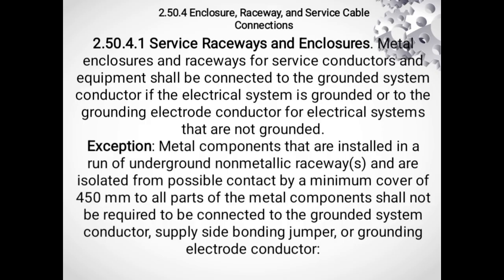We begin with section 2.50.4 concerning the proper connection of service raceways and enclosure. Specifically, 2.50.4.1 dictates that metal enclosure and raceway containing service conductor must be bonded to the grounded system conductor or the grounding electrode conductor. This requirement ensures a low impedance path for fault current, facilitating the operation of overcurrent protective devices. The connection minimizes voltage potential between the enclosure and ground, reducing the risk of electrical shock. Note that this applies to metallic components used to house service entrance conductors.